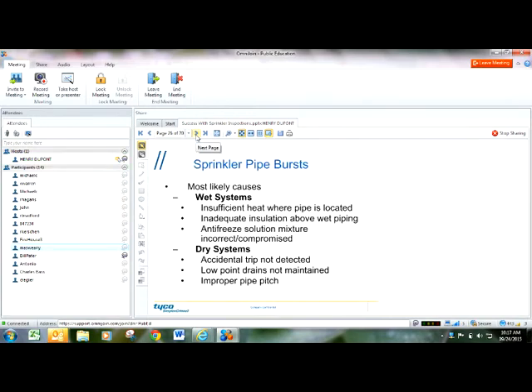Pipe bursts. The most common cause for pipe bursts in wet pipe sprinkler systems is insufficient heat where the pipe is located. An example of that would be a nursing home where they have a wet pipe sprinkler system laying on top of the ceiling with insulation over the top of it. A lot of times that insulation gets kicked off or moved by maintenance people. And then the wintertime comes around and that pipe freezes and breaks. Antifreeze solution mixtures are also not checked and maintained. You've got to have the correct mixture of water with antifreeze in order to keep an antifreeze system from freezing and breaking.